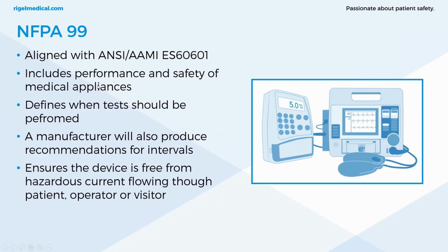So visual inspection, this is aligned with ANSI AAMI ES 60601. We know the performance criteria covers the healthcare environment in its entirety, and not only the performance and safety of the equipment itself. So that's one thing that NFPA 99 differs on. It's talking about the healthcare environment as a whole, not just related to the medical appliances. And a good example of that is the ground and strain relief test on receptacles. They're not medical devices, but it's something that NFPA 99 states, so we have to look at that as part of the procedure.